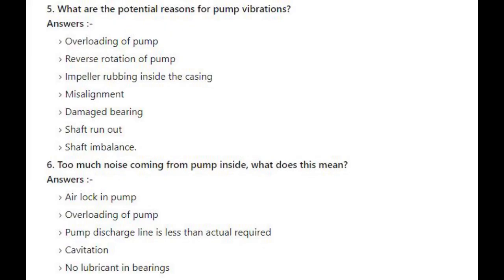Number 5: What are the potential reasons for pump vibrations? Overloading of pump. Reverse rotation of pump. Impeller rubbing inside the casing. Misalignment. Damaged bearing. Shaft run out. Shaft imbalance.